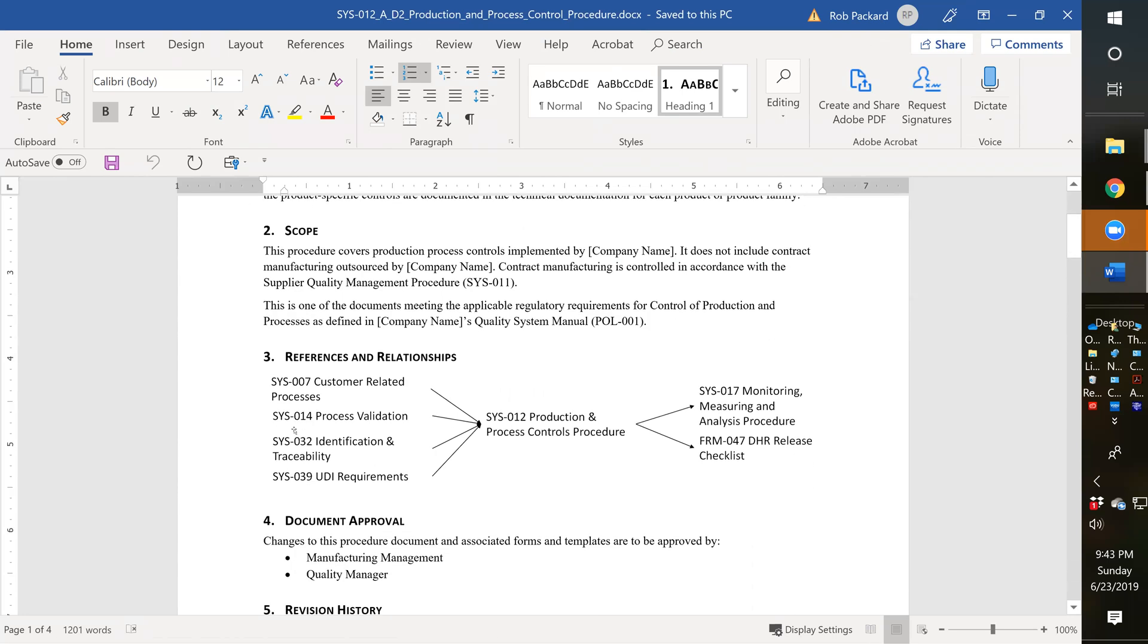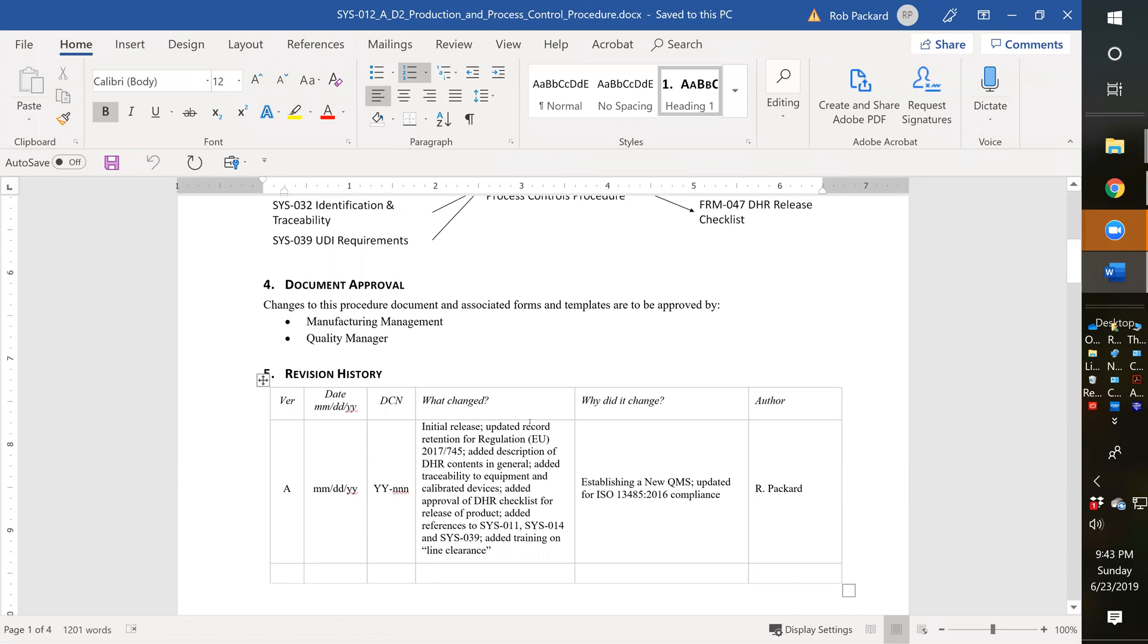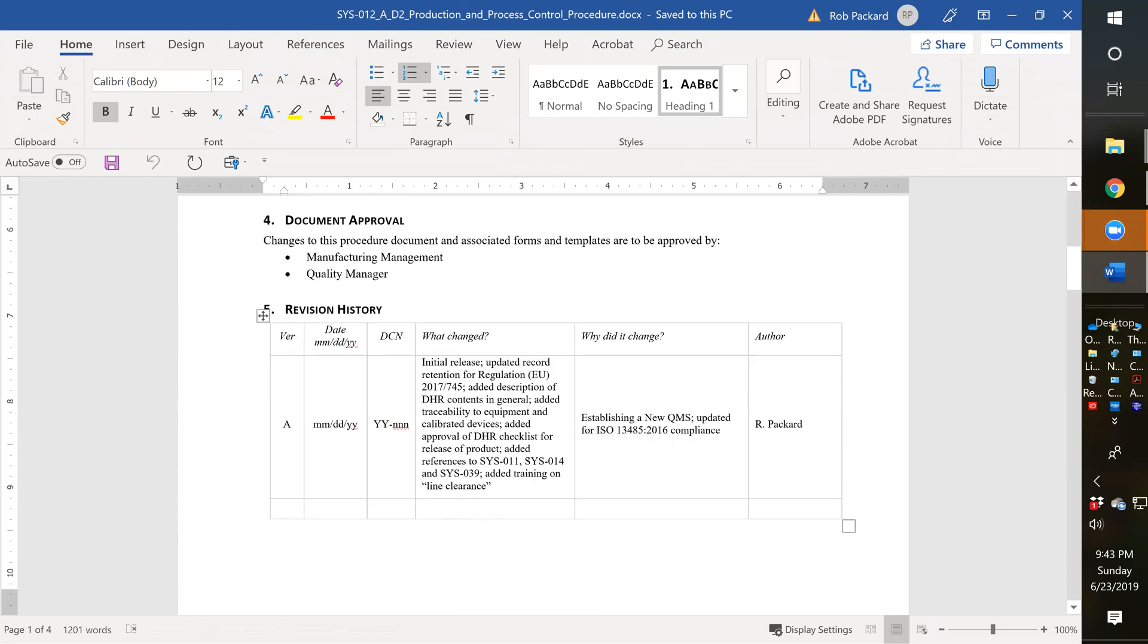Here it shows what the processes are that are inputs and the processes that are outputs and records. It tells you what we've changed in the procedure over time - in this case from draft one to draft two. We've added requirements for the new EU regulation MDR, included description of DHR contents, traceability equipment and calibrated devices, approval of the DHR checklist for release of product, references to other procedures, and a requirement for training on line clearance.